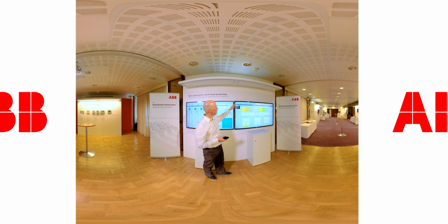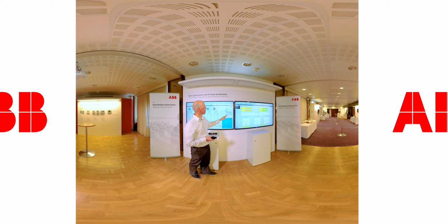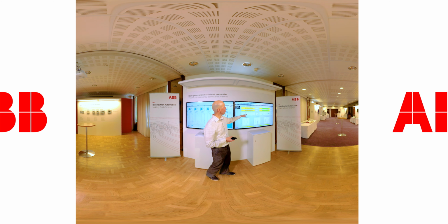So you can see we introduce a high ohmic earth fault. We know the value of the parallel resistor of the coil, in this case 9 amperes. Through the admittance calculation we can see this value regardless of the fault resistance value. And this is the great benefit of admittance calculation. So you can here see that this value of the parallel resistor is seen in the faulty feeder through the admittance calculation.